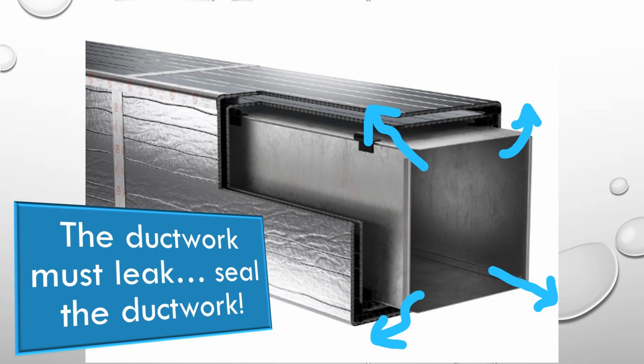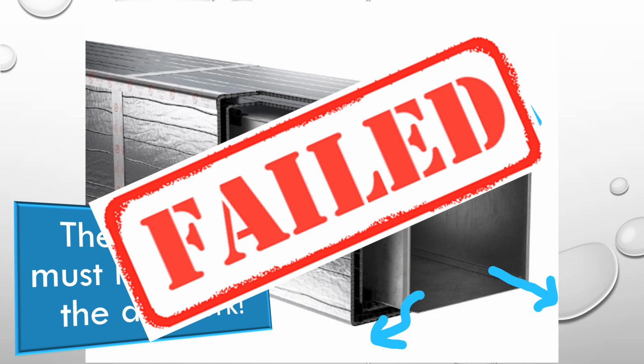So the first thing we thought when it came to condensation issues was the ductwork leaking. We thought there was air infiltrating from inside the ductwork to the outside, just through a gap, just air pushing out. This is cold air hitting the outside of the ductwork. Boom, causes condensation, and now we have sweating ductwork. So we actually bought an air seal machine to stop the leakage inside and seal up all the ductwork. But even with the proven test, we still found out that the ductwork did, in fact, still condensate. So that was a pretty big fail for us.